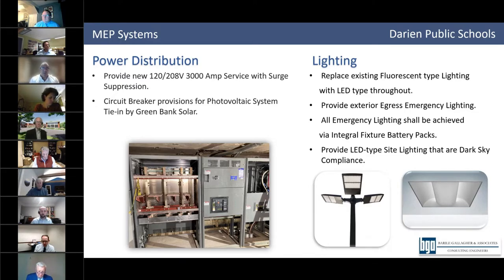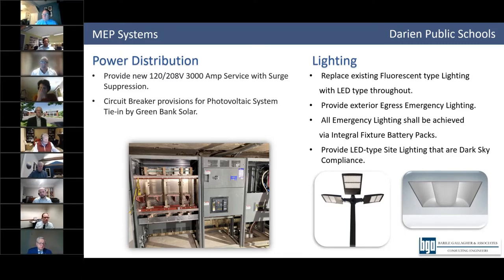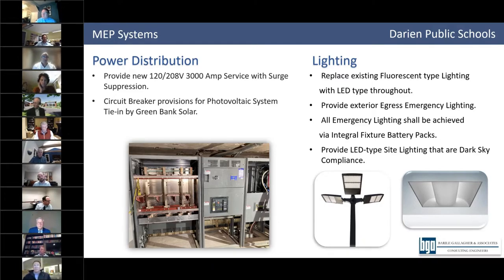On the lighting, we're going to replace whatever fluorescent lighting is left throughout the building with LED type. We're also going to provide exterior egress emergency lighting fixtures. Currently, you only have security fixtures at the doors, and not all exit doors have emergency lighting, so we'll make sure that system is complete at every exit door. All emergency lighting will be achieved via integral fixture battery packs, and we'll provide LED type site lighting that's dark sky compliant throughout.